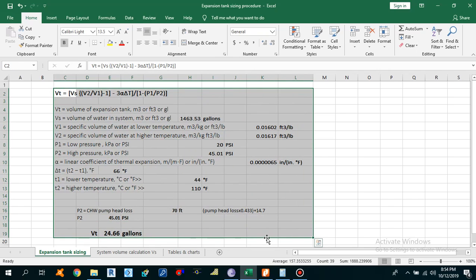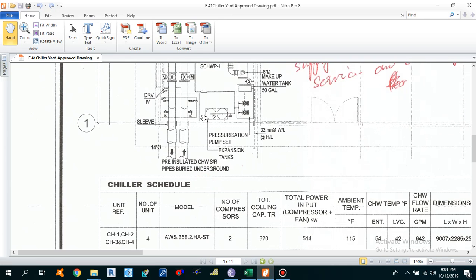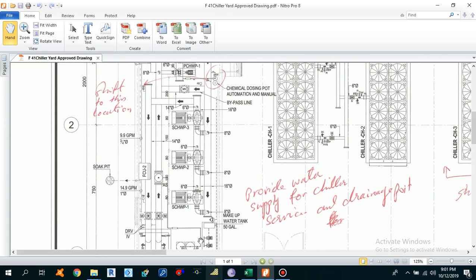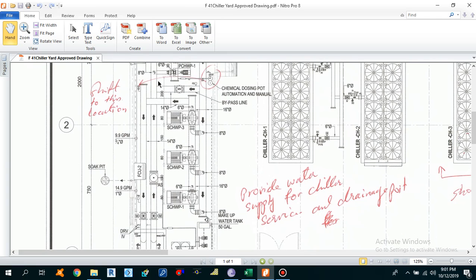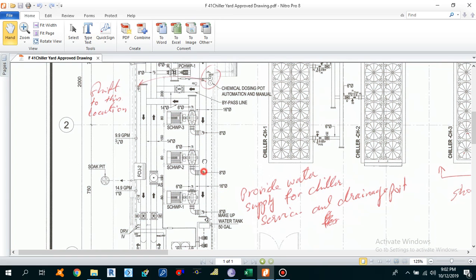The last point is the location of the Expansion Tank. Since the point of connection of the Expansion Tank to the system is the point of no pressure change, it is typically located at the suction side of the system pumps. As you can see in this drawing, the Expansion Tank is connected to the main chilled water return header, which is connected to the suction side of the primary chilled water pump. This ensures that pressure everywhere in the system stays above atmospheric pressure and prevents air from being drawn into the system.